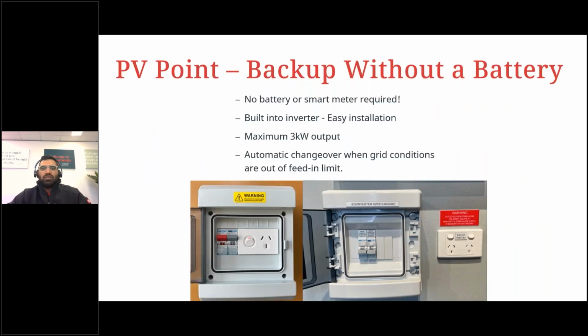So what is PV Point, or this basic backup power supply? PV Point is a socket which is supplied during a power outage or when grid conditions are out of feed-in limits, so it can be really high voltage, no voltage, or low voltage, ensuring that important loads can be supplied. PV Point is an integrated backup power function without any additional cost. We call it a free basic backup power supply, and it can be used with or without a battery.